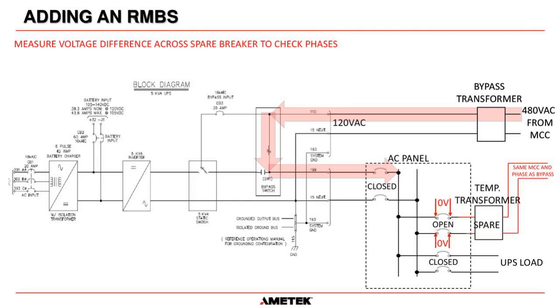Now, do bear in mind that I don't know what the voltages on your plant are going to be, and it could well be that your bypass transformer is 124 volts and this temporary transformer is 121 volts. So there's 124 on this side and 121 on that side, so that voltage reading could be 3 volts. But as long as it's not more than 10 volts, you should be okay. The most important thing is it should be steady. That means they're in sync. It should be absolutely rock solid, steady.